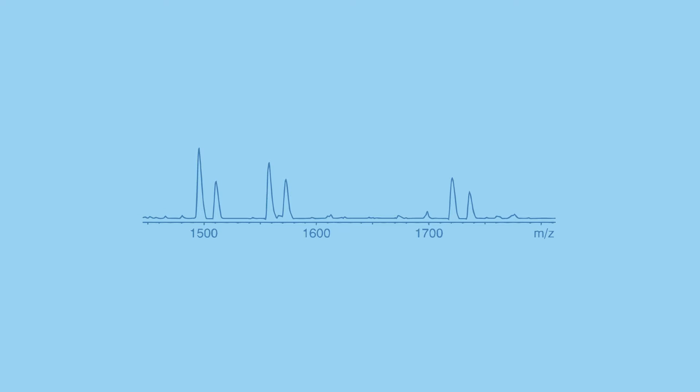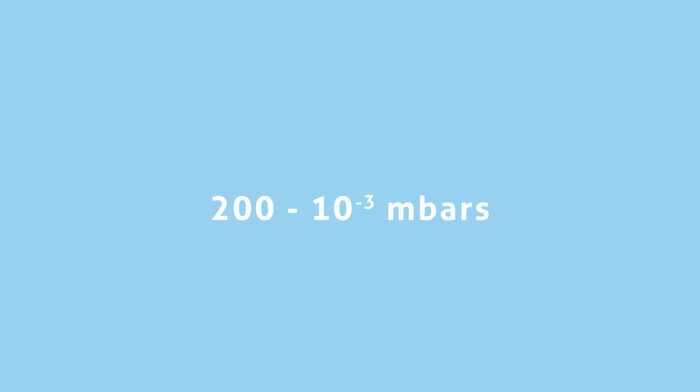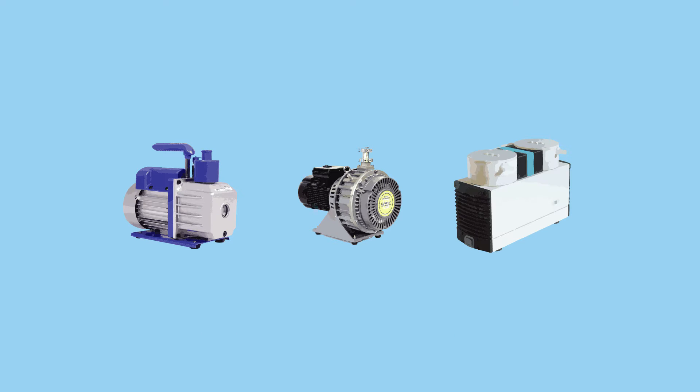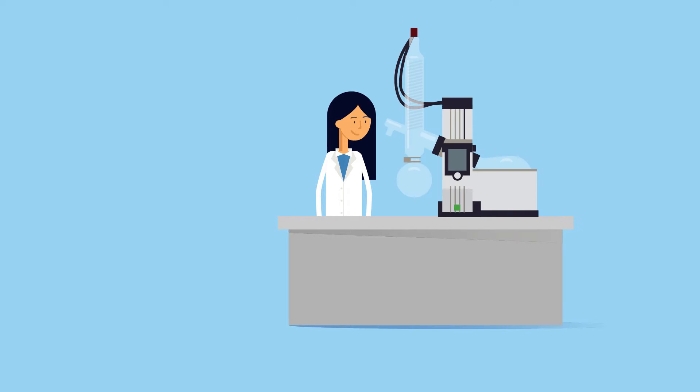A great number of applications use standard vacuum pressures in the range from roughly 200 millibars to 10 to the minus 3 millibar. Rotary vane, dry scroll, and diaphragm pumps all provide vacuum pressures in this range. Linda needs a vacuum pump suitable for evaporation of solvents and knows that when purchasing a new pump for her lab, there are a number of considerations.